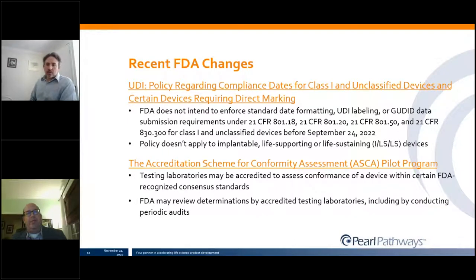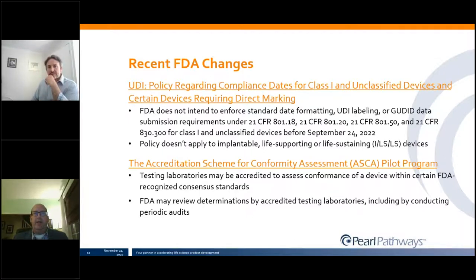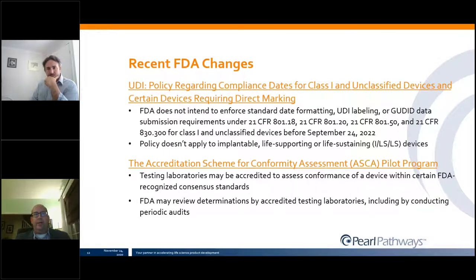FDA also published a guidance on the Accreditation Scheme for Conformity Assessment (ASCA) pilot program, which is designed to accredit testing laboratories to provide data for submissions. Testing laboratories can be accredited to assess the conformance of devices within FDA-recognized consensus standards. FDA may determine if the accrediting laboratory is acceptable during an initial assessment and will conduct periodic audits.